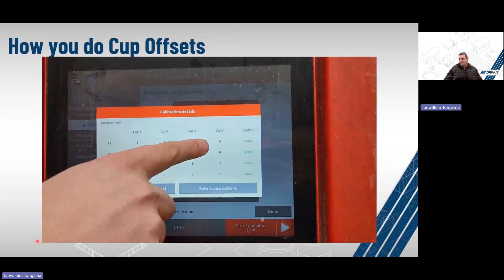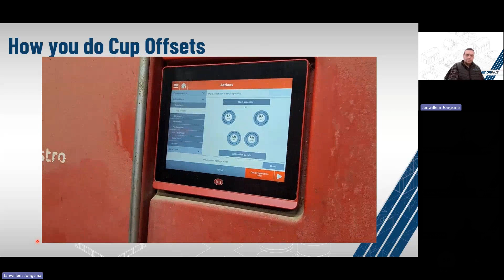And as you can tell now, the scanning is going way quicker than the previous one. See, it's done already. And you can see now the calibration is 0. As good as it's going to get. And now you hit save scan positions and you're done.